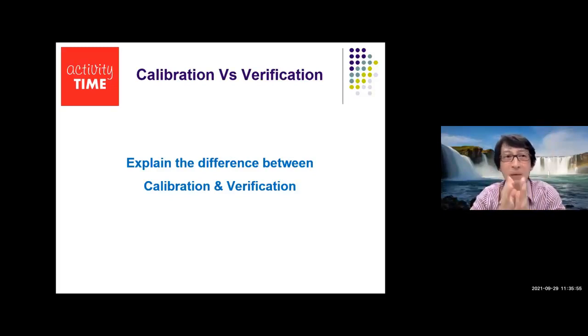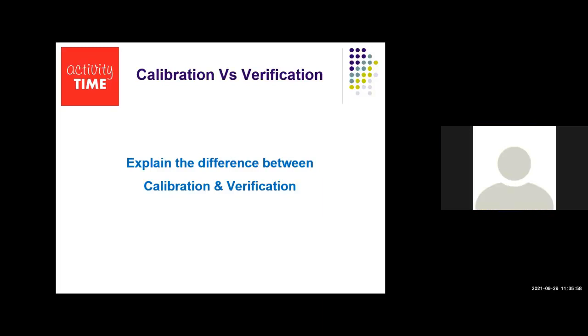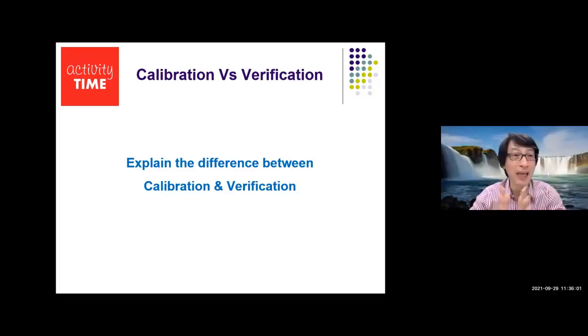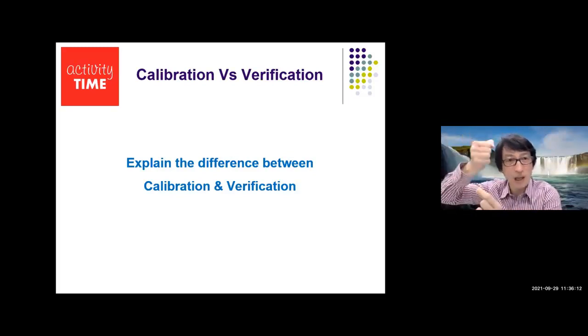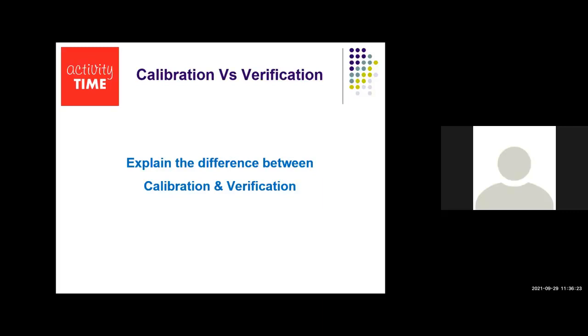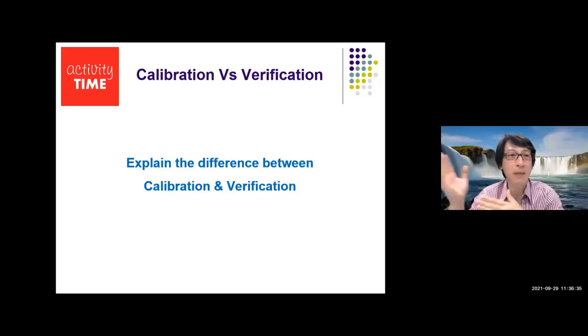Do you need to calibrate the meter? Yes, for everyone, yes. Because if you don't calibrate the meter, you do not know how accurate the meter will be about the value of torque when you put the driver onto the meter, right? It gives you a value. So you need to calibrate. So who does this calibration, in-house or external? Normally for the torque meter calibration, we send out to third-party suppliers. Okay, all right. So you do the calibration by a third-party calibration house, yeah?